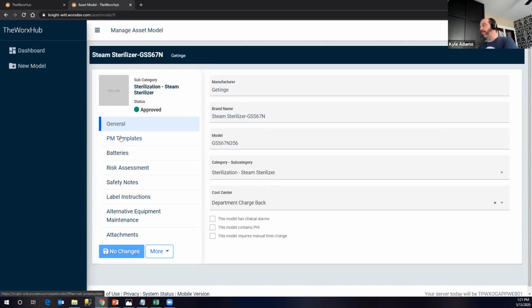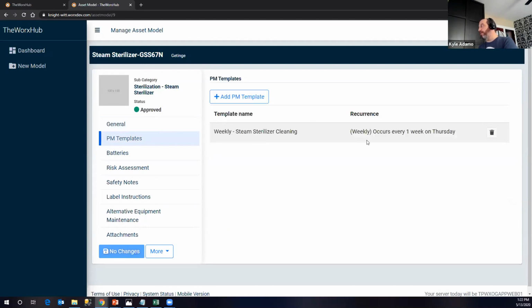We can, for a given model, define what the PM templates are. So we can say here's my weekly steam sterilizer cleaning, I might have a monthly, I might have an annual. You can get all of those defined at the model level so that when you bring a new sterilizer online, all this stuff gets copied forward down to it.